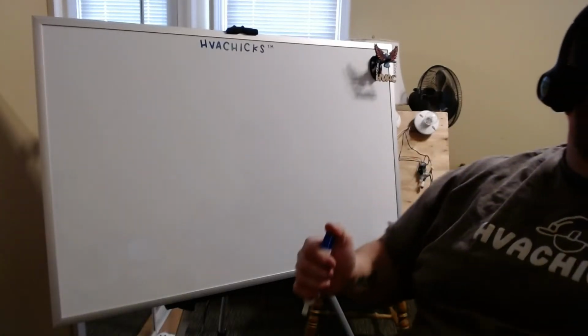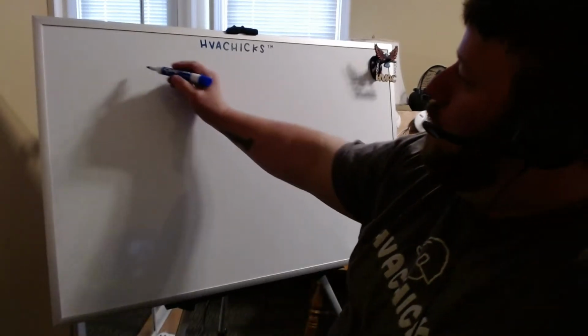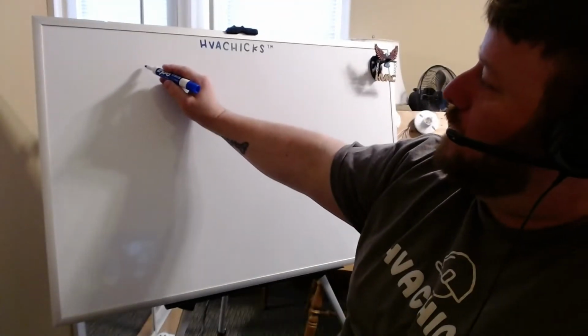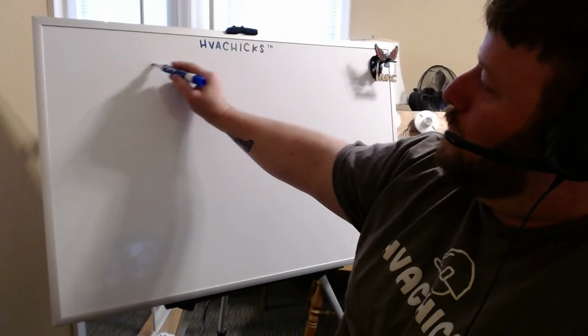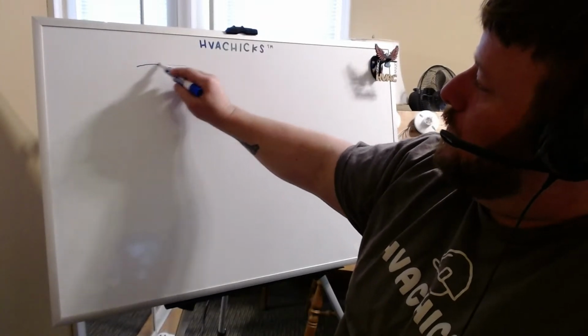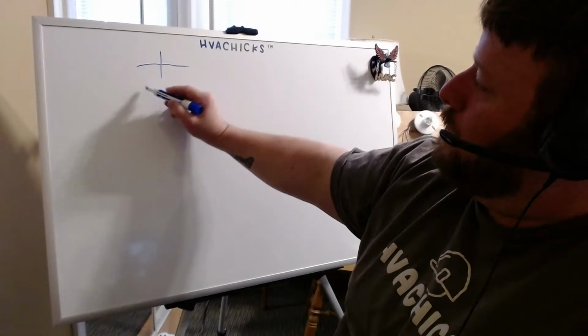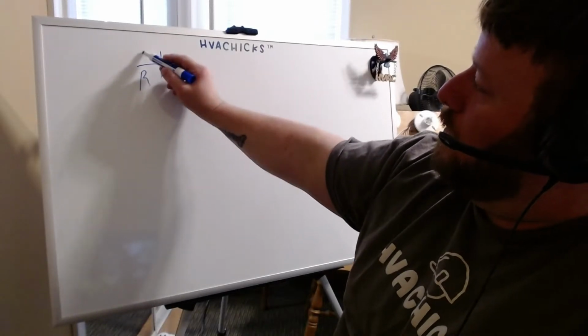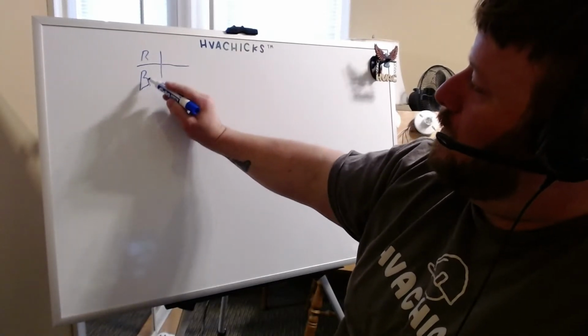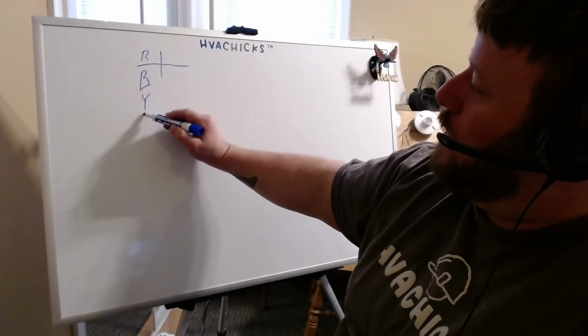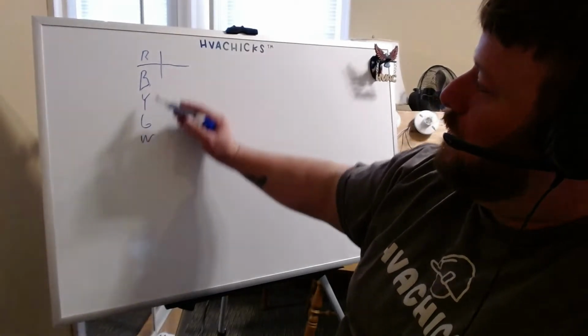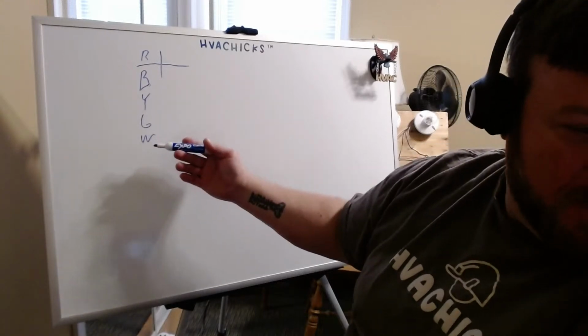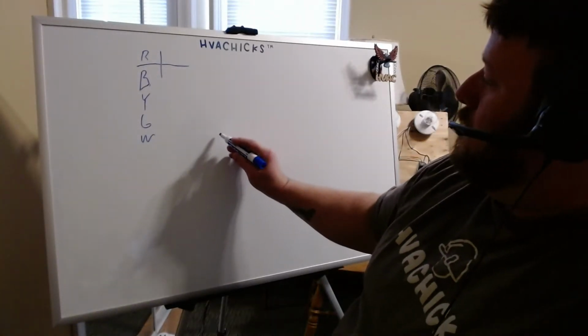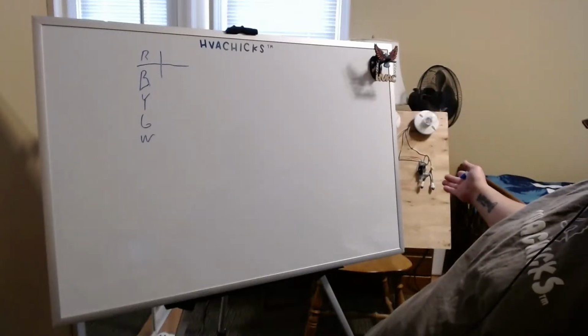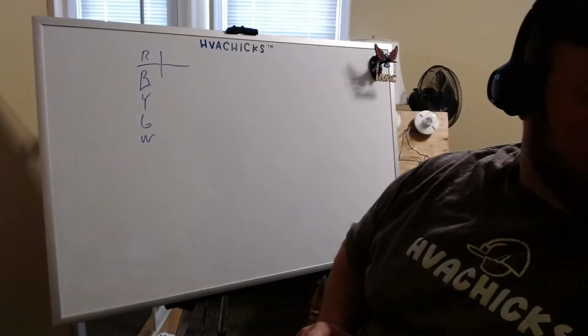So, from the very first class we talked about with wiring, we know when our thermostat calls for heat, our R, B, depending on the heat pump, Y, G, W, those terminals are energized. So I have a defrost board over here on our board.